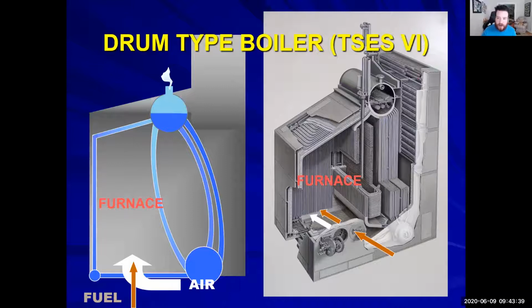So air basically comes in between the boiler wall, where you would think of where the flame is, the inside of the boiler, and the outside wall. There's a pocket there where the air gets preheated by the furnace and it comes in and gets sucked in that way. That adds some efficiencies. It also keeps the boiler from becoming too hot, as far as what you're concerned about it being on the outside of it.